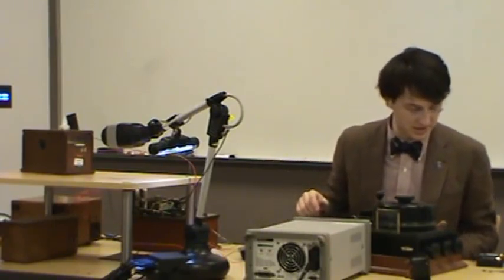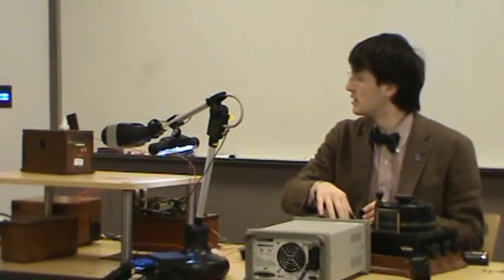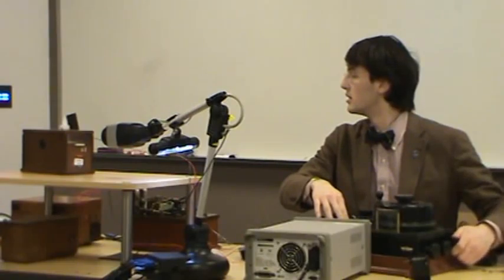I'm going to recheck against the standard cell to make sure the balance was okay. And it is not. Something has drifted here. Must have bumped it. That would cause this to not be able to balance like we did before. If you have any questions, feel free to ask them right now because I'm just watching the moving light like you are. But fortunately, I can think about more things than just that. Well, that's balanced again. So now we go back to this.